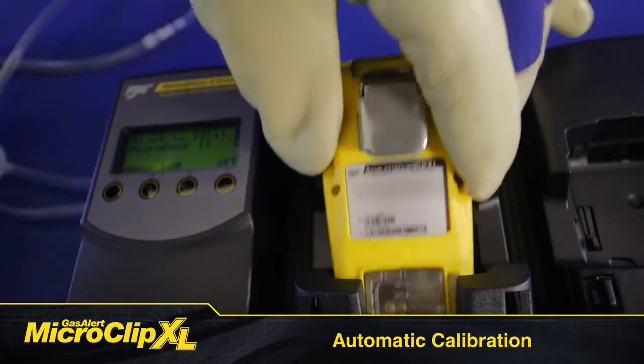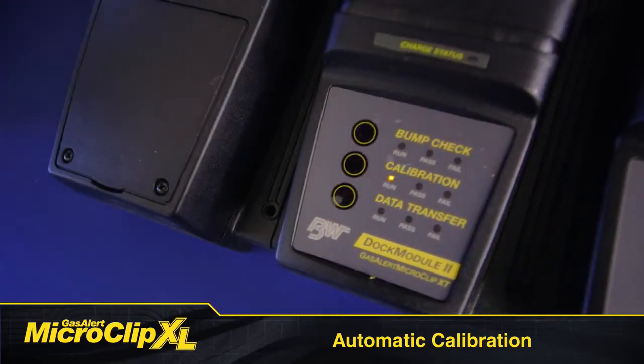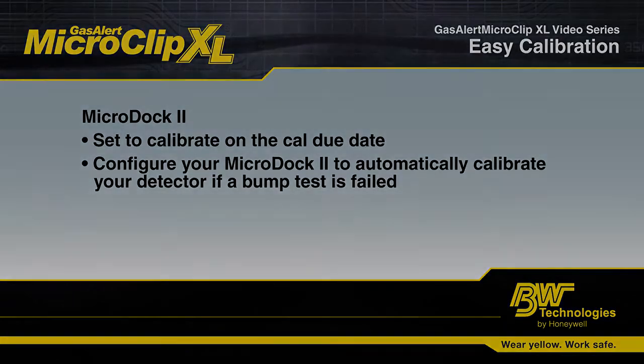Automated calibration is super simple with a MicroDock II. Make sure your detector is turned on and then just put the GasAlert MicroClip XL into the dock. Push the calibration button to start calibration. Your MicroDock II can be configured to automatically calibrate on the cal due date. The system can also be set up to automatically calibrate in the event of a failed bump test.